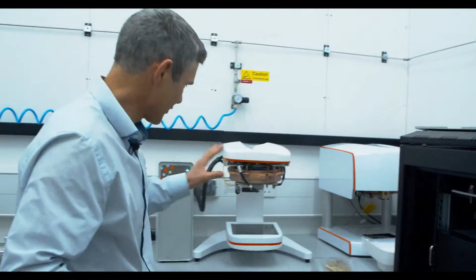And today we're going to be imaging some antique hand bones. So these are held together with little bits of plastic twine to keep them in position. So I'll place those on the detector. We can go outside of the bunker and we'll start the acquisition. Okay, so we're set up to image a hand, and you'll hear the Geiger counter go in a minute as the emitters fire from lots of different positions, covering lots of different angles. And once we've acquired all of that, we can do some pre-processing and calculate what 3D shape created those shadows. And very soon we'll have a slice through the middle of those bones.